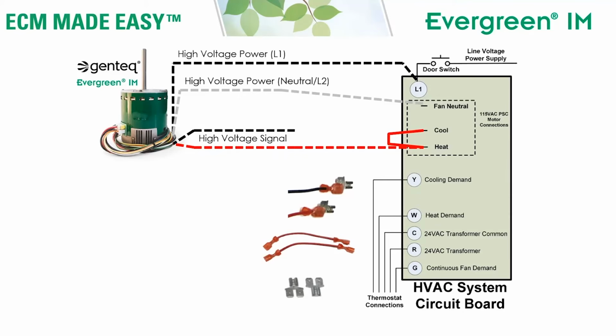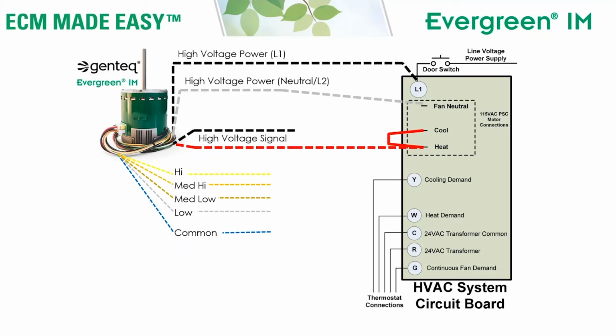And again, we provide the wires with all the 1/4-inch terminals and Y terminals and extra jumper wires needed to get this job complete. So again, you don't need any terminals out of your bag, and you don't need any new wires. Last but not least, we're going to select our speeds for heat and cool, now using the 24-volt side of the system. So we're going to connect the blue wire from the new motor to transformer common.